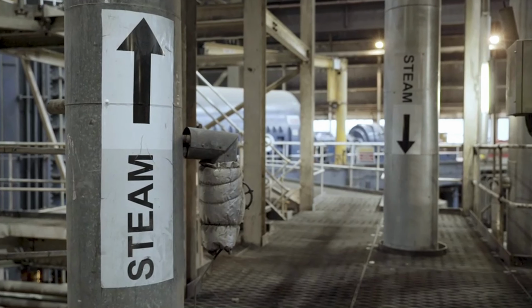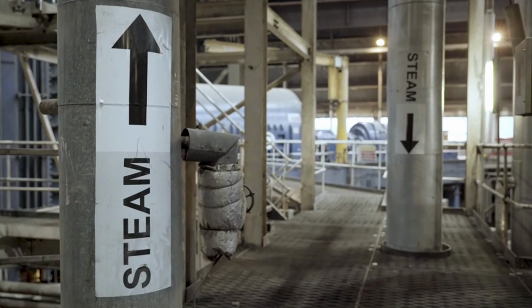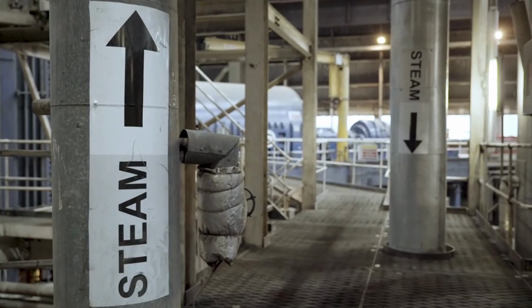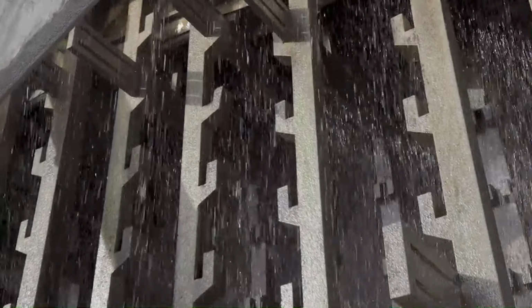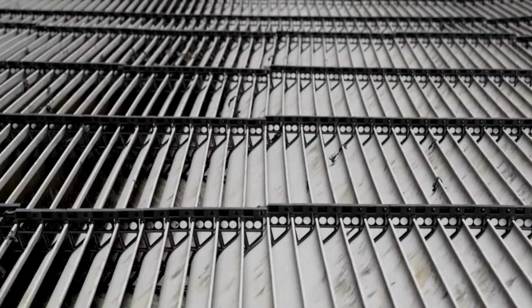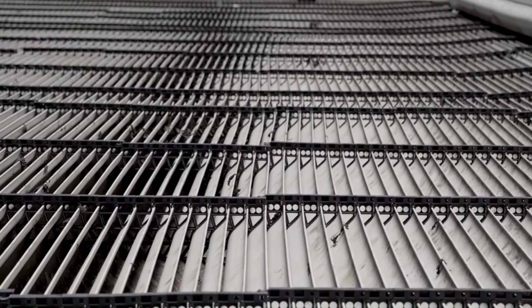So how do they work? The cooling water enters the tower through a series of pipes and is transferred to a manifold containing hundreds of nozzles which spray the water evenly onto a fill.